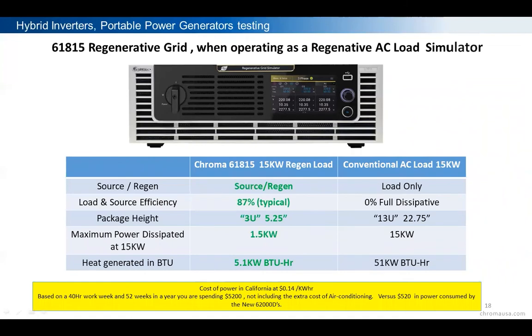So the grid simulator also, when it's used as a load, has regenerative capability. So when you compare that to a standard load is fully dissipative, meaning any energy it gets from your device is dissipated into heat. Creates a lot of heat, needs a large heat sink or a lot of additional cooling to keep that unit operating properly. The device is going to be much larger. It's going to be 13U or bigger for 15 kilowatts. It's going to weigh a lot more. It's probably going to weigh 400 or 500 pounds, to be quite honest, in some of these large loads.